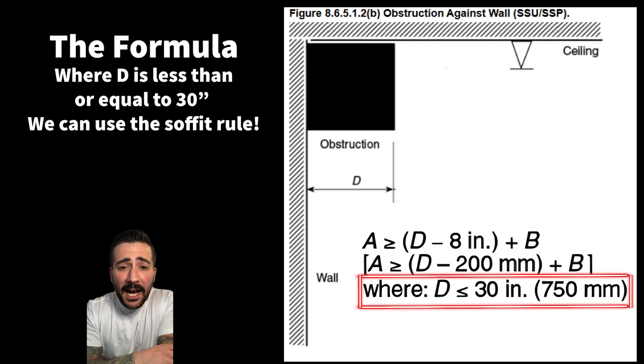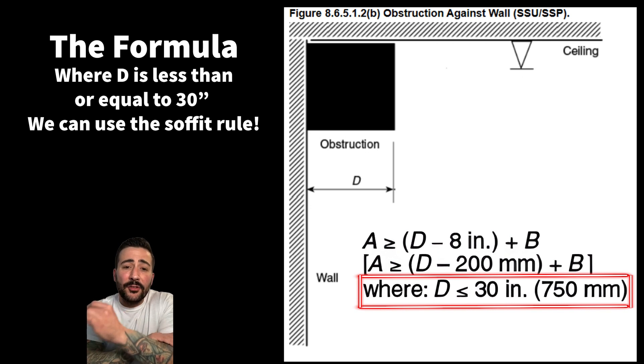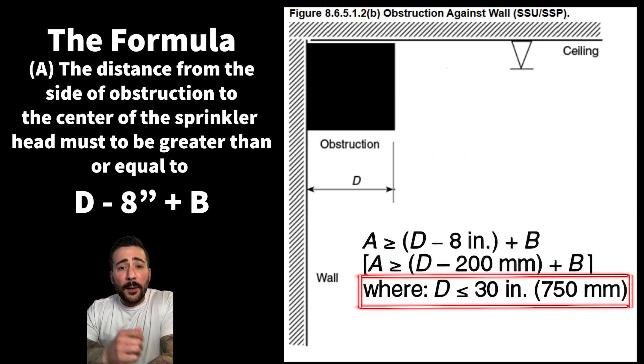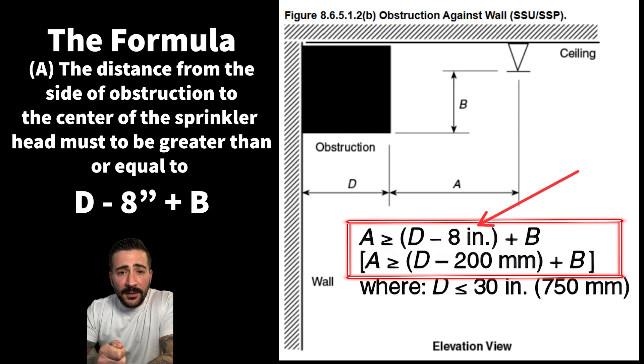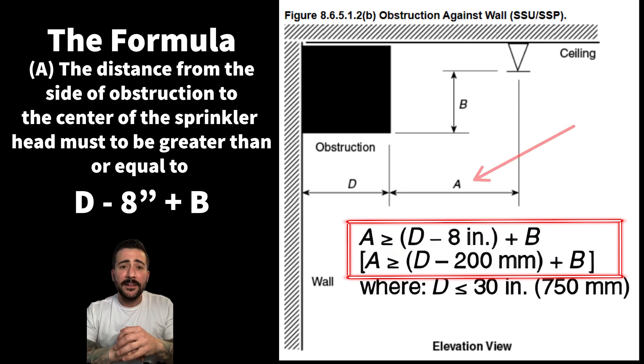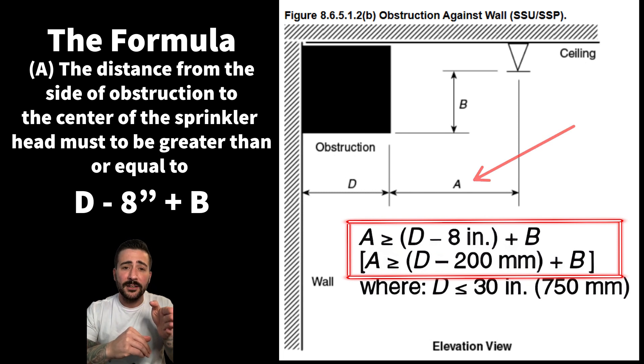Now on to the formula. First thing we have to make sure is that D is 30 inches or less. If the width of the obstruction is 30 inches or less, we always minus eight inches first. Then we add the distance from the bottom of the obstruction to the sprinkler deflector — we add those together and that will give us A, the distance from the side of the obstruction to the center of the sprinkler head.